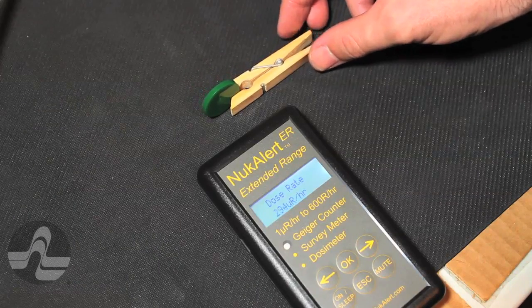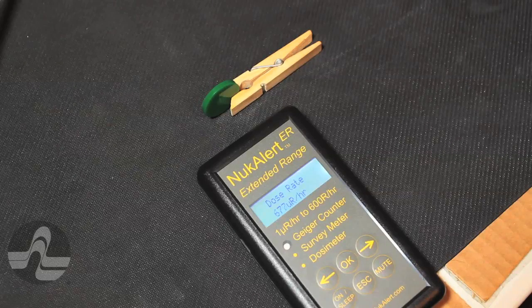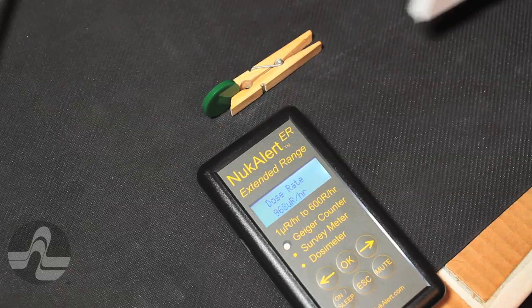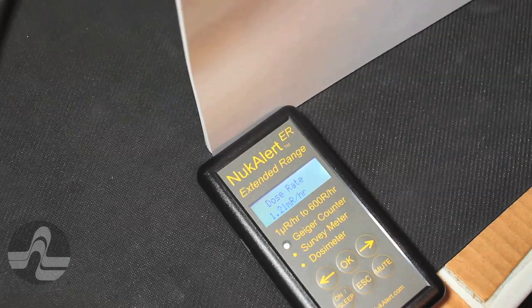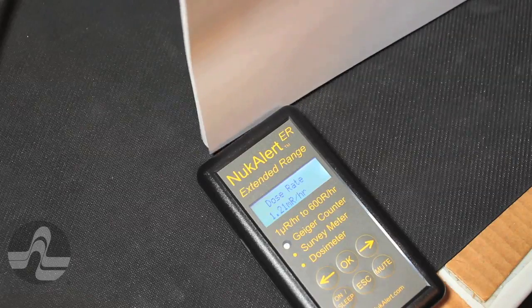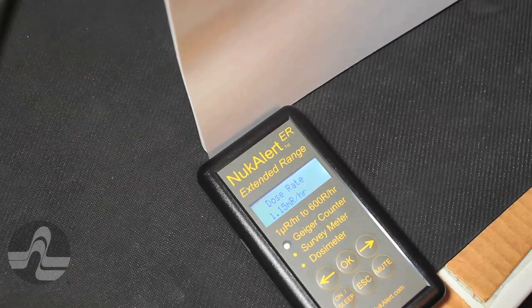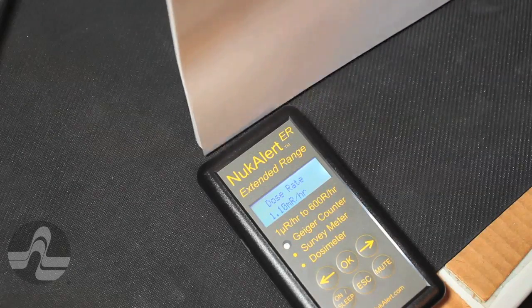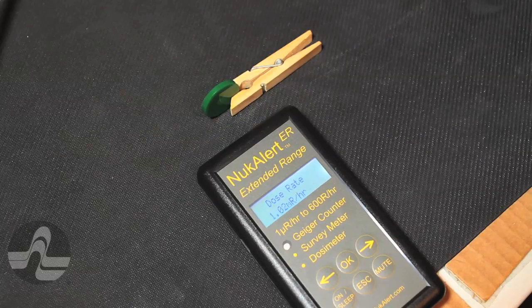This is a 0.1 microcurie strontium-90 source being blocked by a quarter-inch stack of paper to illustrate the instrument's beta sensitivity. Most traditional Geiger counters with sensitivities comparable to the NukAlert ER would be close to saturation at the count rates demonstrated here.